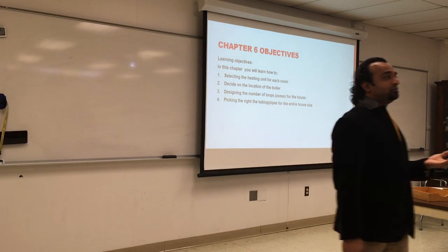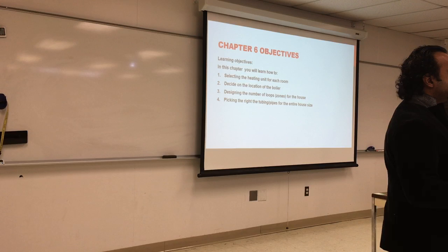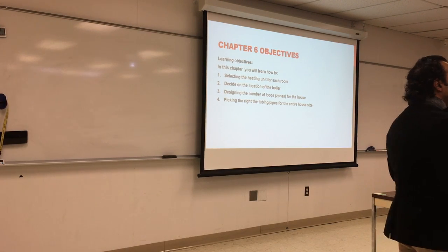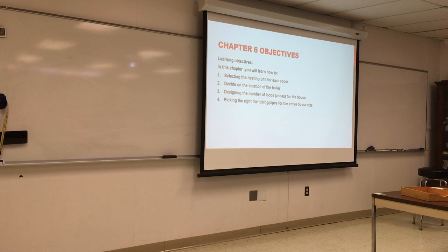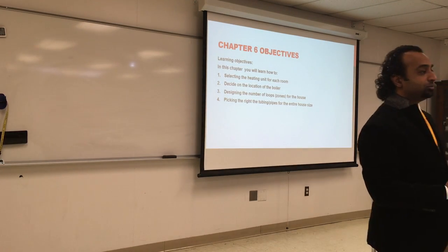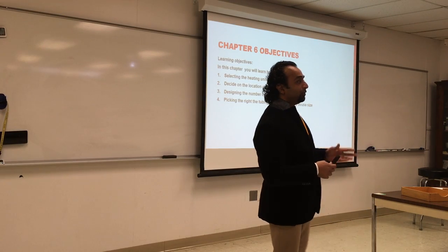When I was looking at the IBR reference, it's a little bit not intuitive to follow the sizing. I'll give you some formulas you can think about. I know it's easier just to follow a table, but just as common sense, the mass and amount of water that comes in is the same amount of water coming out. Whatever water you put into the pipe, it should come out of the pipe. So if you have more branches coming into the tube than there is trunk of the tube, you're not going to have an even distribution. I'll illustrate what that means.